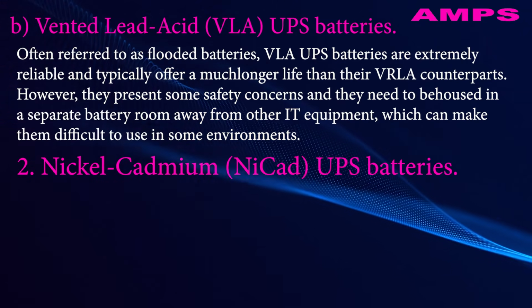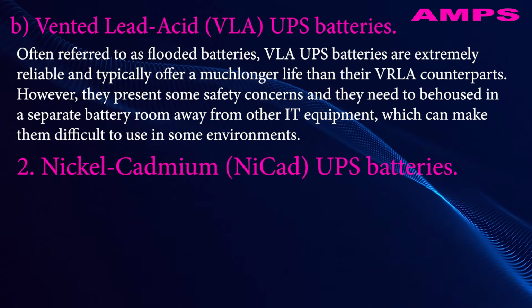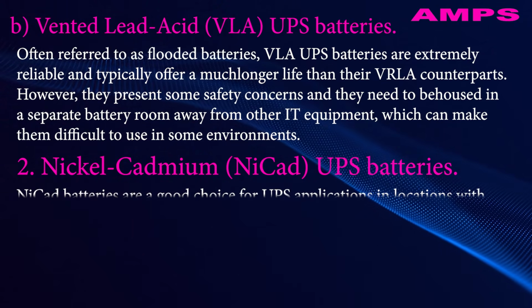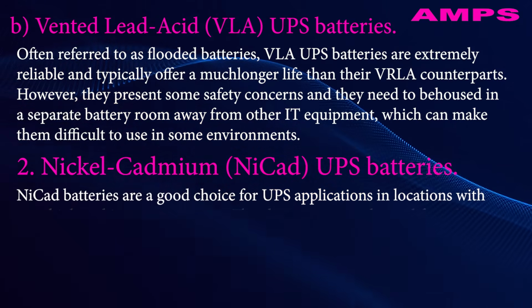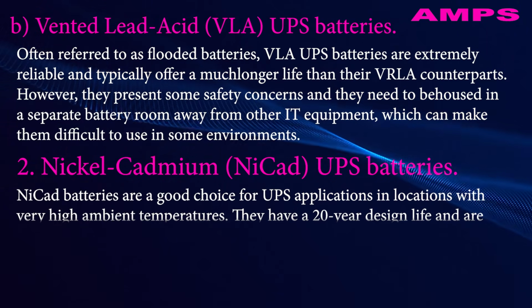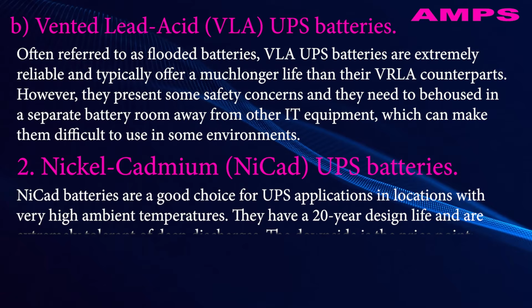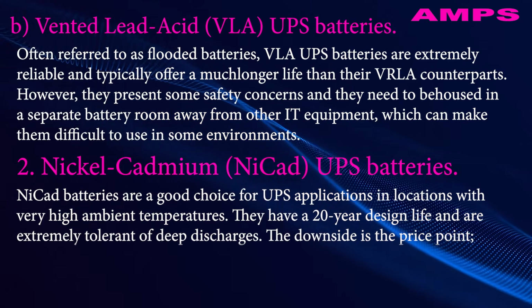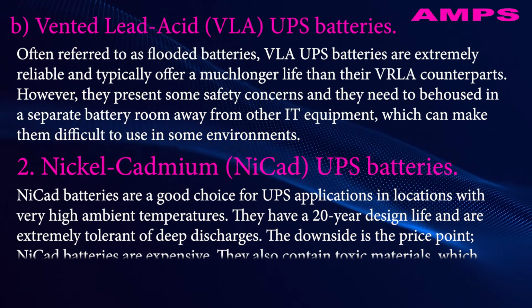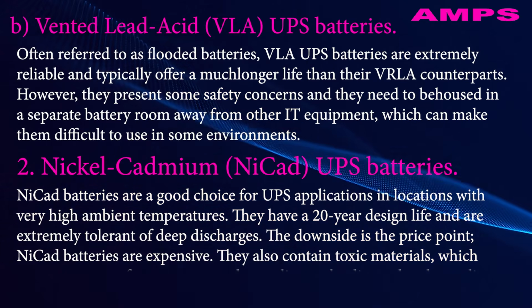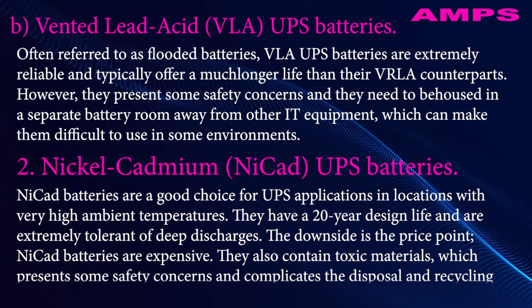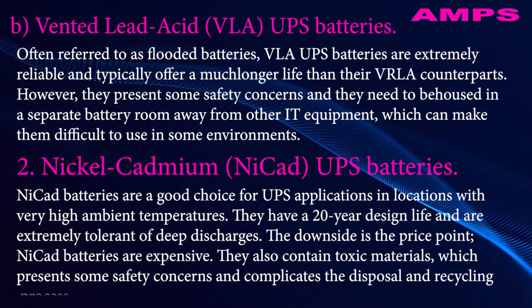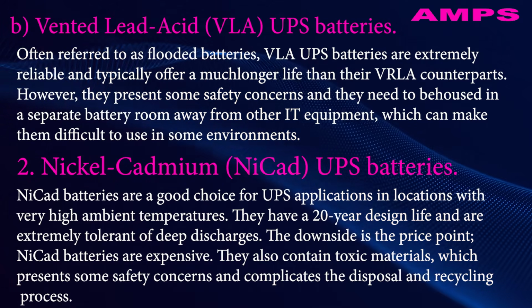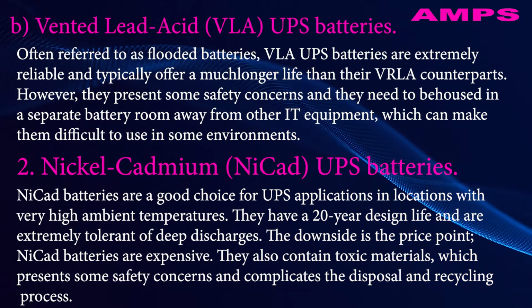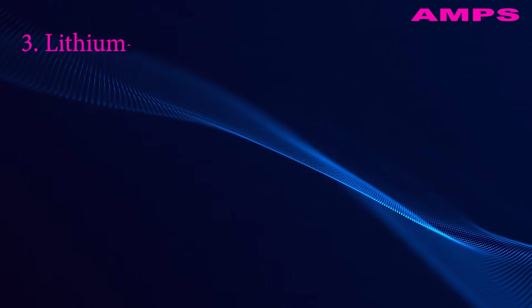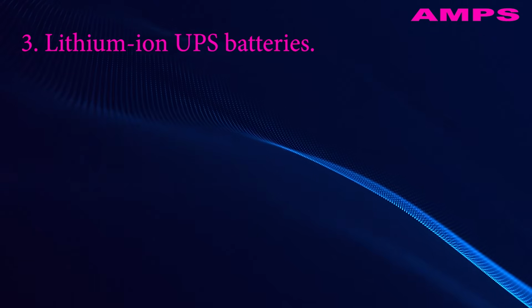Nickel-cadmium, NiCad, UPS batteries. NiCad batteries are a good choice for UPS applications in locations with very high ambient temperatures. They have a 20-year design life and are extremely tolerant of deep discharges. The downside is the price point. NiCad batteries are expensive. They also contain toxic materials, which presents some safety concerns and complicates the disposal and recycling process.